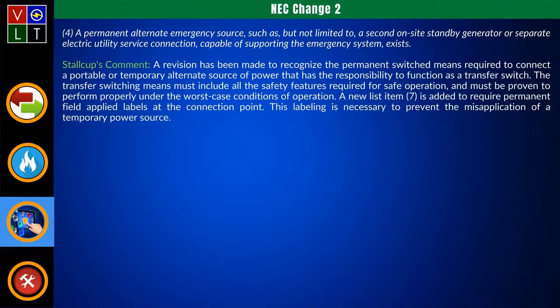Safe operation, and it must be proven to properly perform under the worst case conditions of operation. And regardless if you have a temporary source of power, it's still a permanent switching device. So sure, you have to treat it as a permanent part of that electrical system. So I think that's good. I don't see anything wrong with that one.